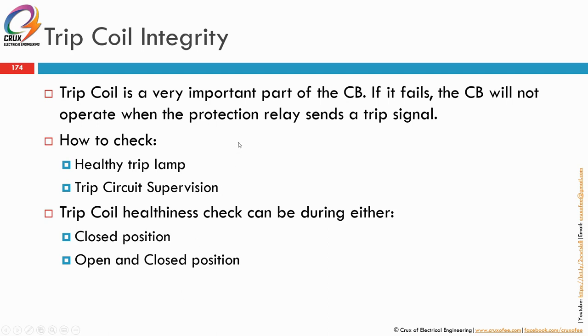Number one is we have the healthy trip lamp. This is the old type, the old version of the trip circuit supervision lah. The second, modern type is the trip circuit supervision. So in most protection relays, the circuit has been designed to include trip circuit supervision monitoring.